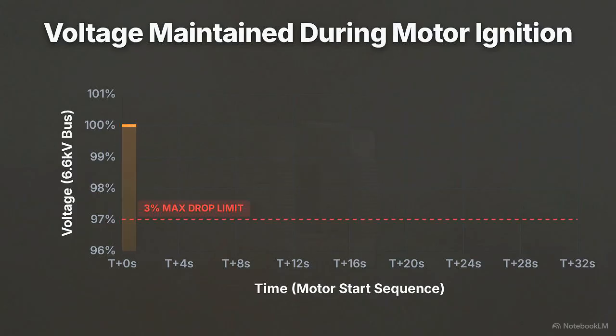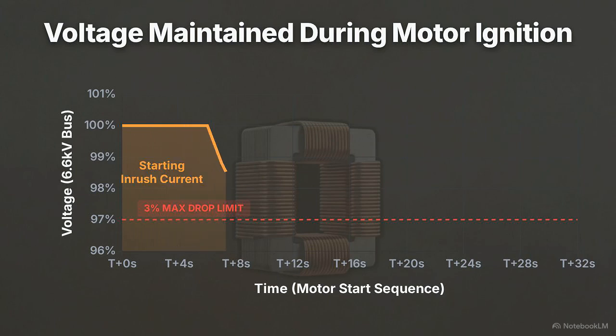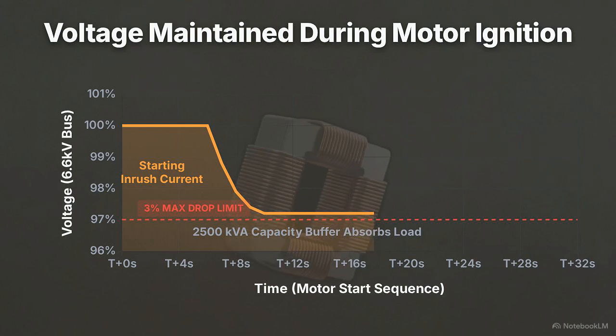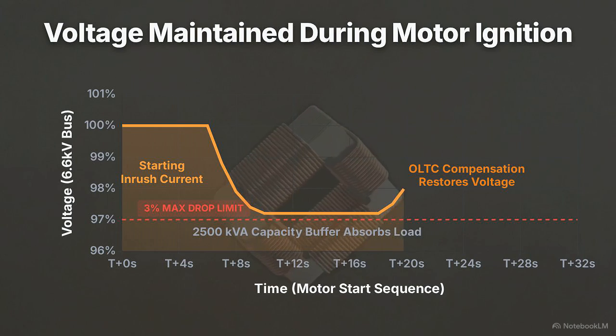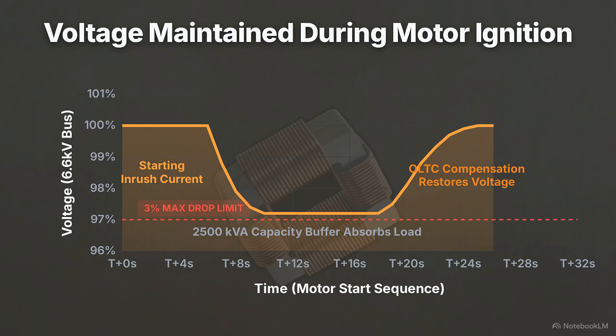This chart plots the electrical grid voltage over time during motor ignition. The 2500 kVA rating provides enough magnetic bulk so that when the massive 650 kilowatt motors draw their starting inrush current, the downward voltage spike precisely halts before crossing a 3% drop limit, preventing overheating. As the line chart dynamically corrects itself and shifts upward, the tap changer adjusts internal coil ratios to feed a perfectly stable 6.6 kilovolts to the motor bus.